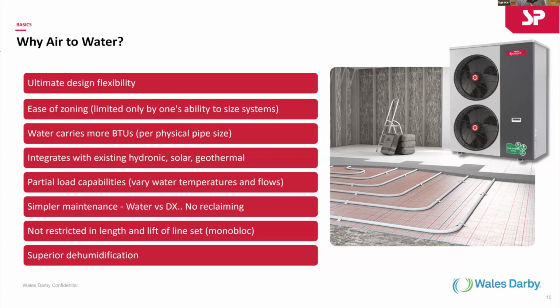And the beauty in it is you can really foul up water and it'll still work. As long as you can make piping do loop-de-loops, as long as the water gets there, it'll transfer either the cooling or the heating. It lends to tremendous room for error. Okay. Whereas, as you guys have been experiencing with the world of refrigerants, unfortunately, it's not very flexible. It has to be sized perfect and it has to be installed perfect.